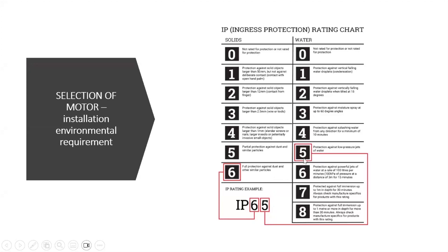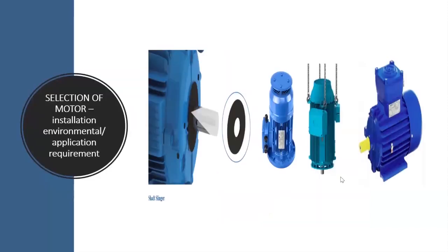In terms of the solids and in terms of the water, is protection against jets of water at a rate of 100 liters per minute at 100 kPa pressure at a distance of 3 meters for 15 minutes. So based on your application, you choose your right IP rating. Else you go and install a motor with a wrong IP rating and you risk the chance of losing the motor in no time. And in terms of the installation also, the installation environment is very critical.